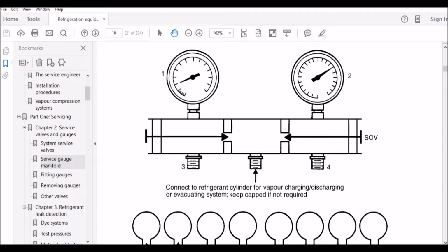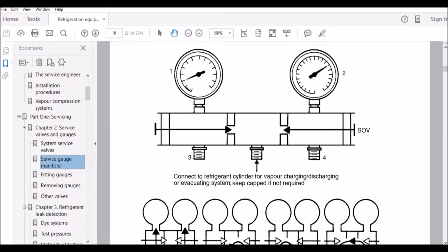Now, the other thing that you will have noticed once I did that is that no gas came out of this yellow line, and that's because I didn't do anything with my shut-off valve. So my manifold shut-off valve was closed, okay? And because it is closed, that basically means that the refrigerant went straight to the gauge and didn't actually enter into the manifold chamber, all right? So therefore, no refrigerant escaped out here through this yellow one.